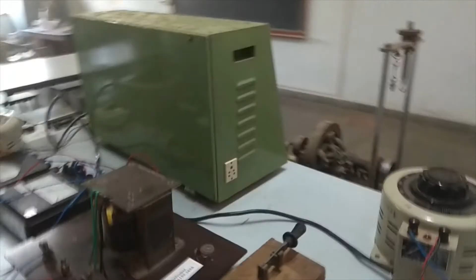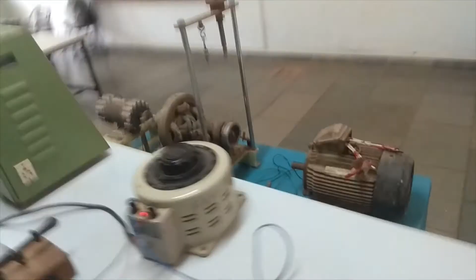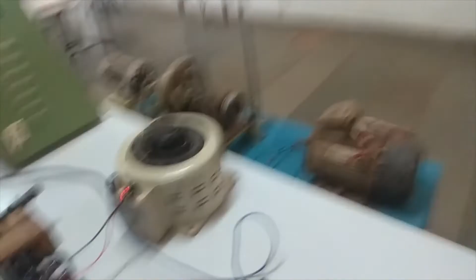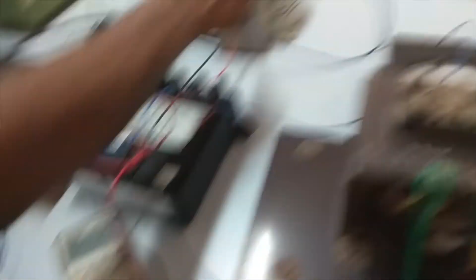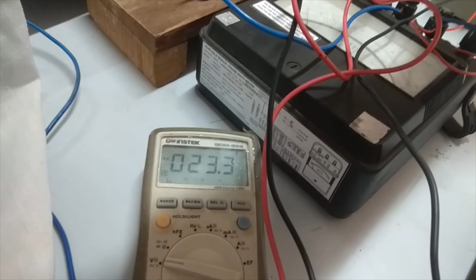Now we can close the switch. This knife switch can be closed, and then we will switch on the supply for the second transformer. Note that the variac should be at the 0 position, and we will increase the variac, injecting the voltage so that the rated current flows. So we are going to measure how much voltage is injected so that the rated current is flowing. We can see that it is coming around 23.3 volt. So this is the voltage. Now both supplies are on, so we can note down the readings in our observation table.